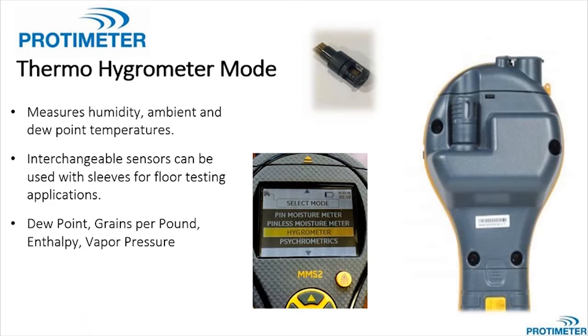The next mode of measurement with the MMS2 is very important to remember for concrete testing, because you're measuring readings of relative humidity. The MMS2 has a removable sensor mounted on the back of it that measures humidity and ambient temperature. That sensor is removable, so if you ever need to buy additional sensors, or if you drop it in water and it gets damaged, you're never without your meter. You just buy a new sensor and you have the full functionality of that meter without having to give up your meter to send it back to us for service or repair. You simply replace the sensor.